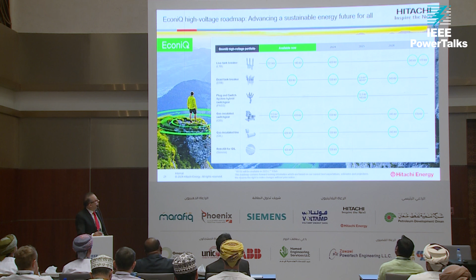As I said, we use a different gas mixture in the live tank breaker versus the MEB, metal enclosed breakers. Here we use CO2 plus O2 in the LTB, and in the other one we use CO2 plus O2 plus C4FN.